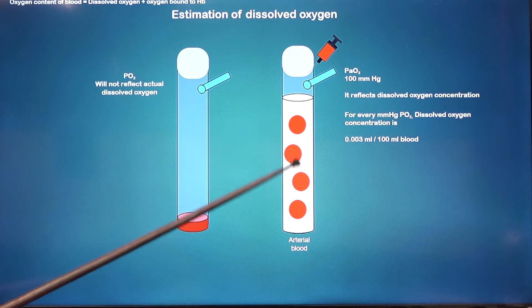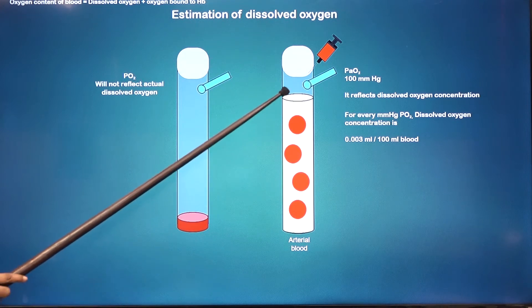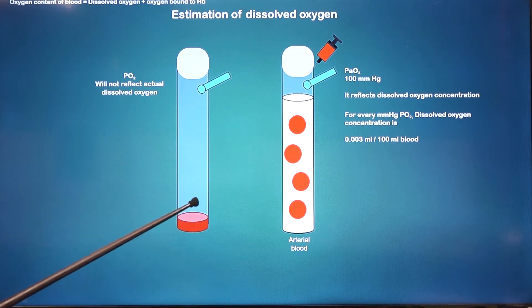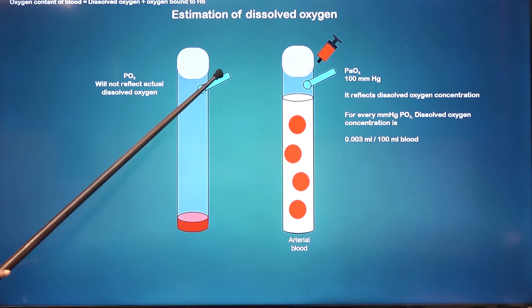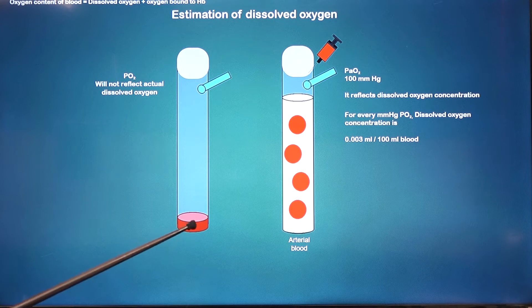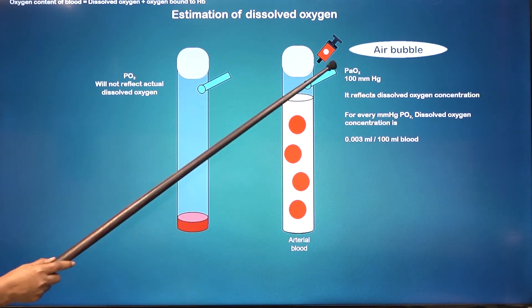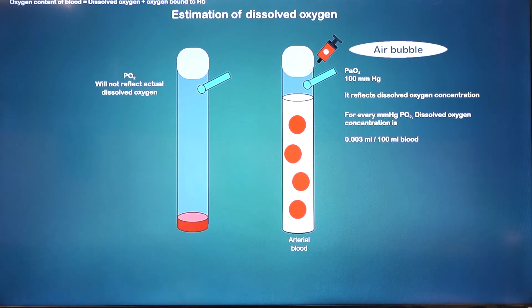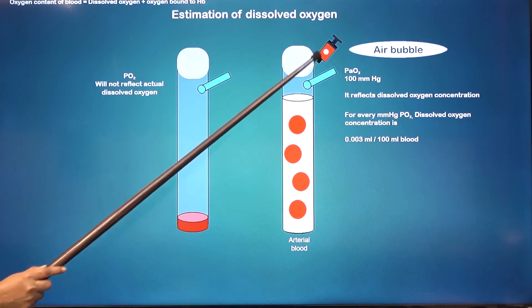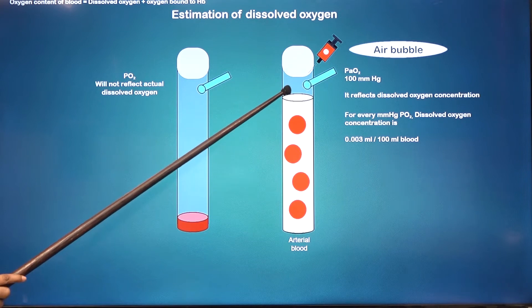If instead of filling the test tube with enough blood and leaving only a small airspace, you took less blood and there was a lot of airspace, then after equilibration the measured partial pressure would be more reflective of air than blood — you would overestimate partial pressure of oxygen in blood. The same argument holds if there was an air bubble in the blood sample; the oxygen in that air would also contaminate your reading.